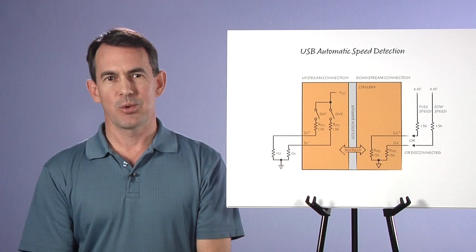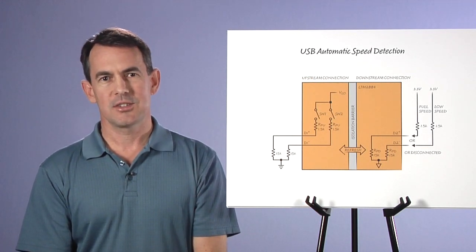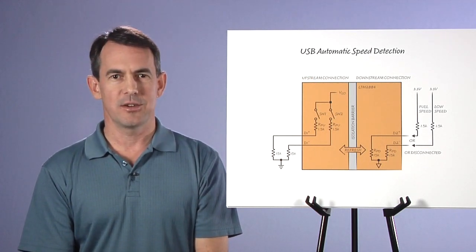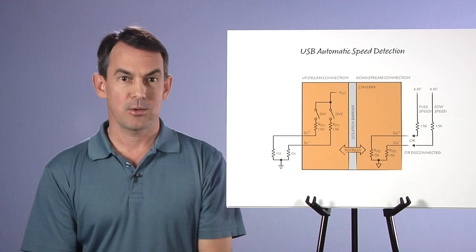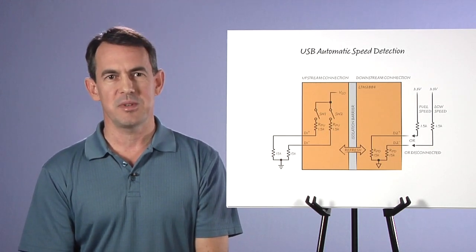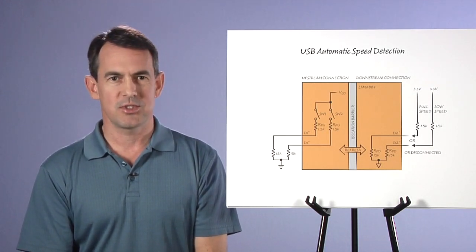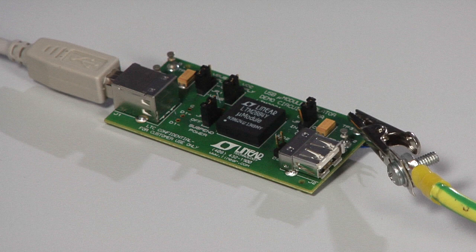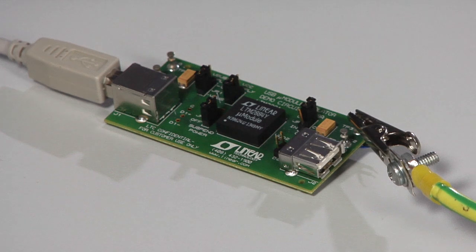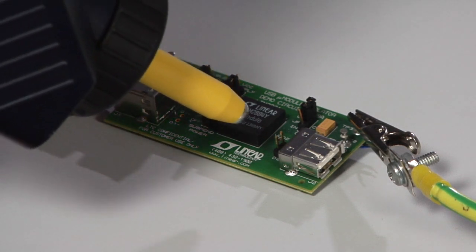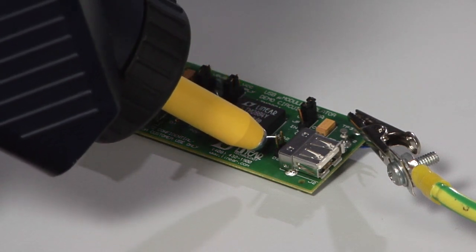Before discussing more operational performance, I'd like to show you the robustness of this USB interface. After all, this product is for isolating USB in harsh industrial or sensitive medical environments. Here, I'll zap a data pin directly with 20,000 volts IEC Air Discharge ESD. You should be able to see and hear the physical spark as I bring the tip of this ESD gun toward the post connected to the D2-plus pin.